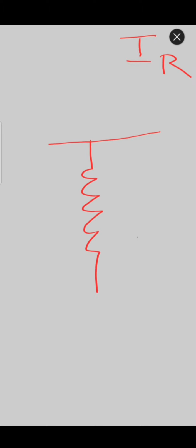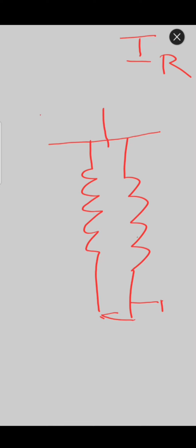This is the CVT. Okay, this is the LV point and this is the HV point. HV point is connected to, let's say, a 110 kV line. So before performing the tan delta, the equipment on which the tan delta testing is to be done must be isolated from the live part.